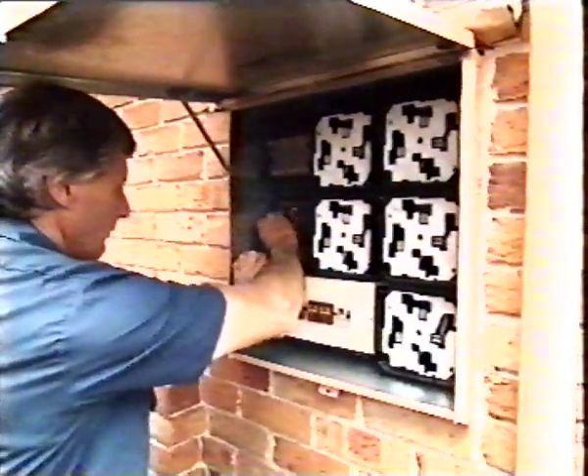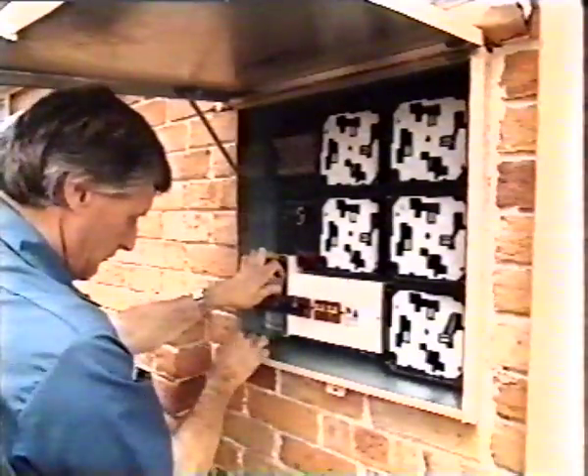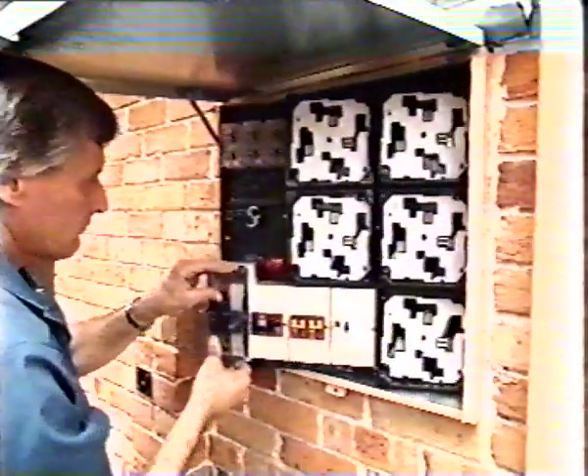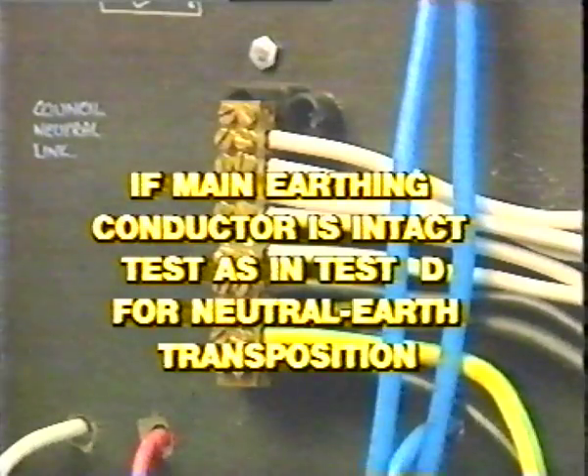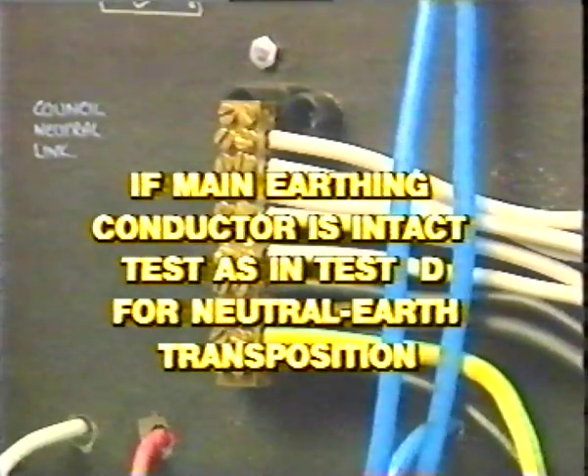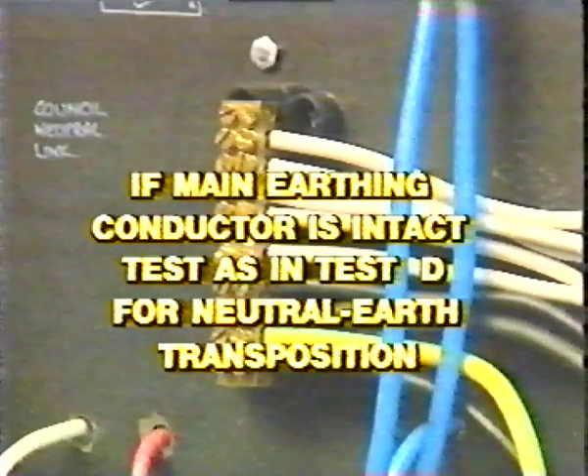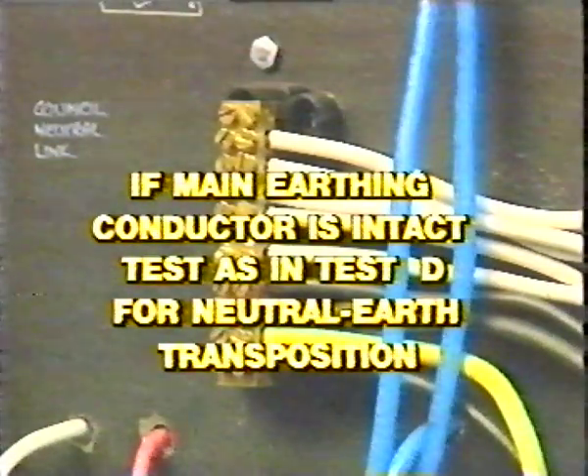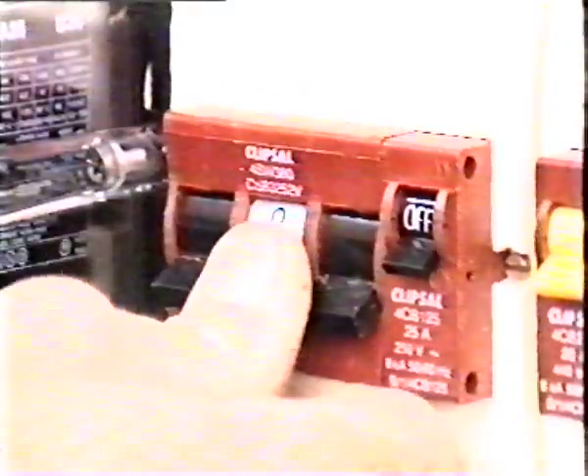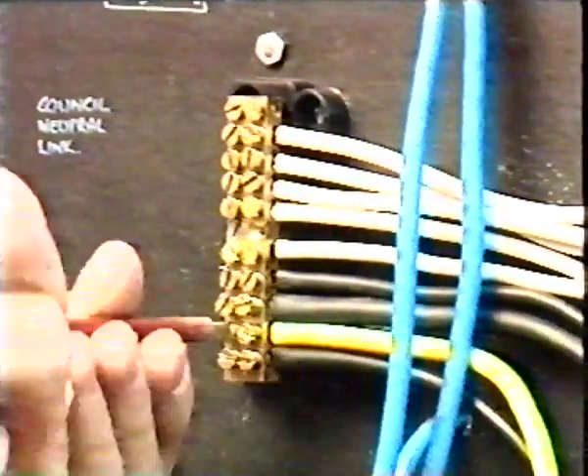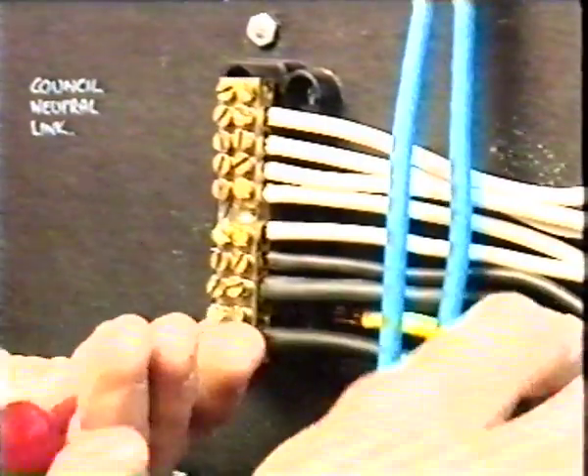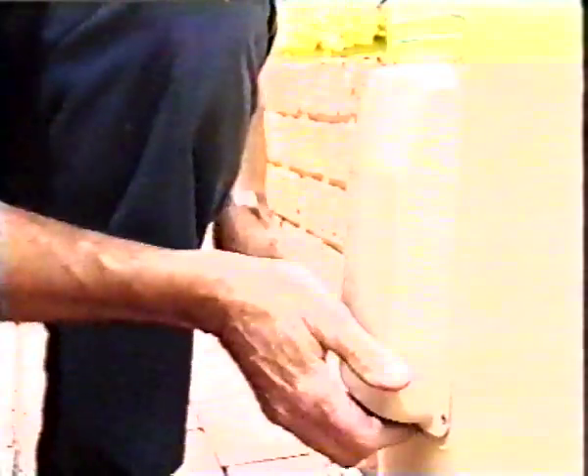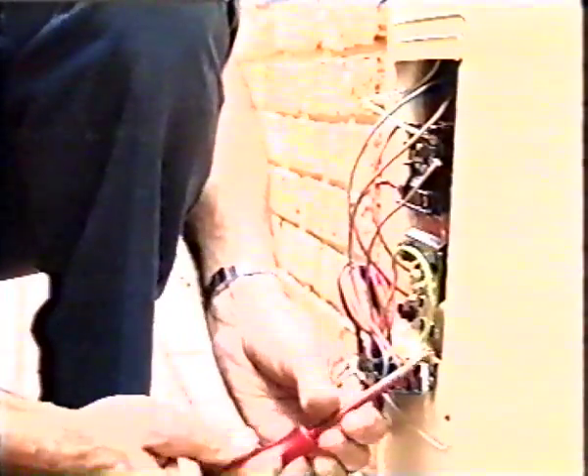The test procedure requires the main earthing conductor to be disconnected from the neutral link at the MEN connection, so as to exclude the possibility that earth continuity is detected via the neutral conductor. Should the test be performed with this connection intact, subsequent tests are required, such as shown in Test D, to establish that neutral and earthing conductors are not transposed. First, open the main switch, then disconnect the main earthing conductor from the MEN connection, and then the earthing conductor at the water heater. Disconnection of the water heater earthing conductor ensures that there isn't a parallel circuit via the water piping system during this test.